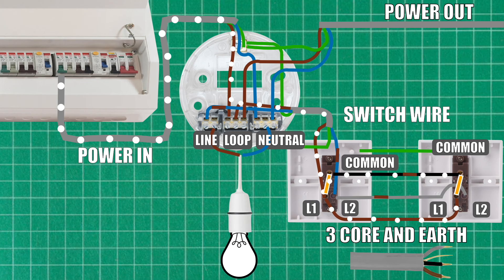We can clearly see here there's no path back for the electricity until you click one of the switches again. And another thing that's important to do is, as indicated where these arrows are, you want to put a little bit of brown tape on these wires to indicate that they're switched lives. The color codes might be different in the country you're watching this from. Now there are various other methods of wiring up a two-way switch, but this is my preferred method. So now that's all the wiring done, and it is worth noting here you should only be carrying out this kind of work if you're a competent or qualified person. I hope the video has been helpful to someone, and thank you for watching.